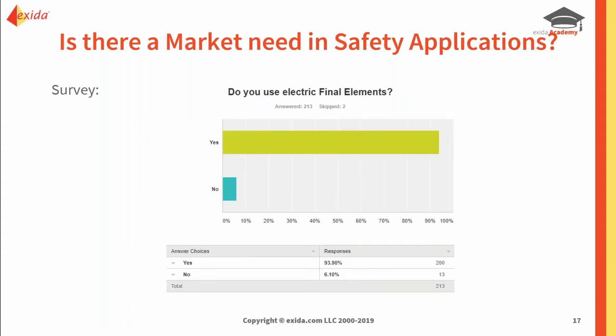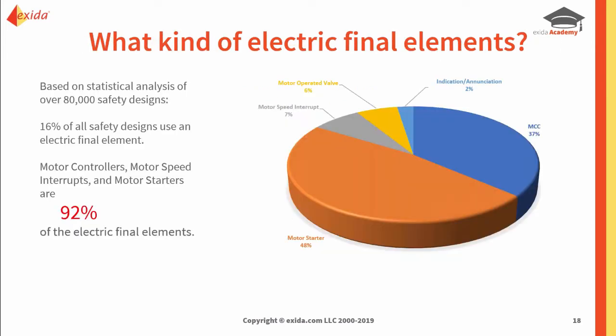So why would we have this influx of motor controller webinars and seminars that we've been giving? Because there really is a need. The ISA, the International Society of Automation, I just said that wrong, did a survey, and when people were asked, do you use electric final elements, literally 99% of people said yes. Then you break it out: based on 80,000 SIF safety designs, 16% of all safety designs used an electric final element. Of that 16%, how many were motor controllers, motor speed interrupts, motor starters? You can see here 92% of it.